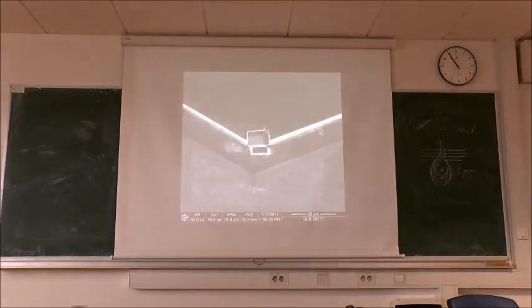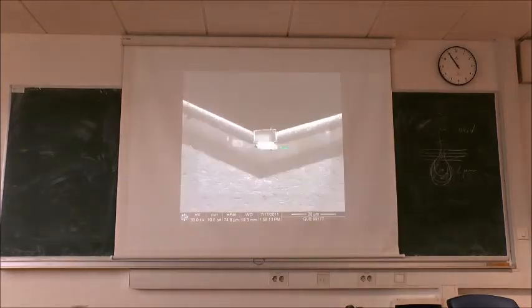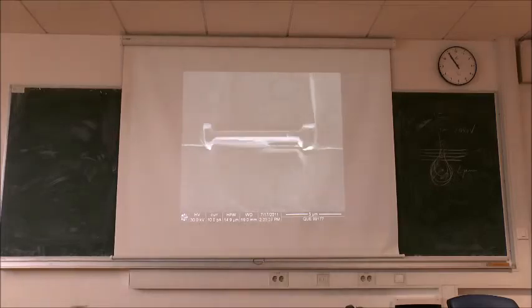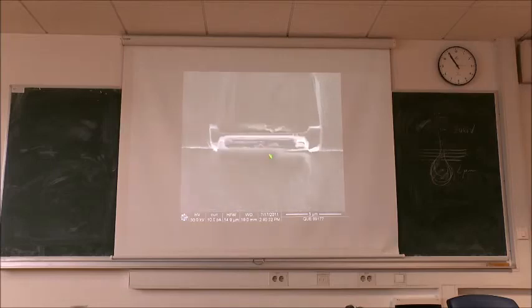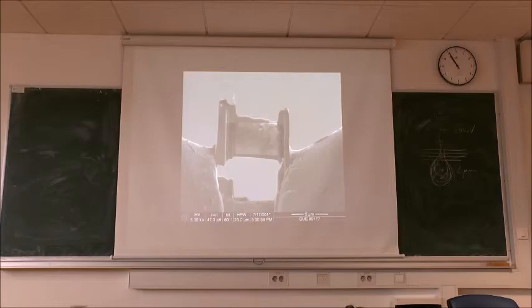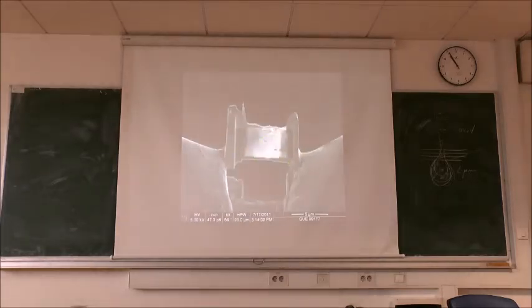Okay, maybe the final or semi-final act: now you have to really do fine thinning of your lamella. Still, I would say it's maybe something like 2 microns, definitely too thick. But if you can go down to 50, 70 nanometers, maybe like this one here, and especially again using low energy, so that you will not end up with an amorphous lamella. At the end, you see here, some areas are really, really thin. And that's it, the happy end.